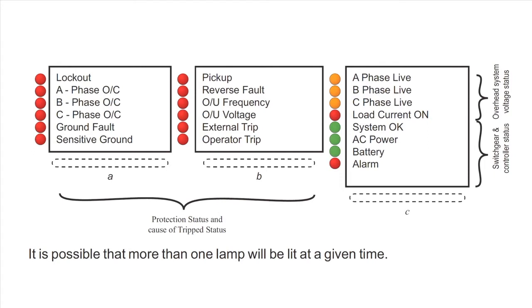The third bank of status LEDs provides information regarding the switchgear and control status, as well as the overhead voltage status. A, B, and C phase live. The source or load side bushing of the relevant phase is live. These 3 LEDs are orange in color when active. Load current on. This LED is red when a load current of more than 2 amperes is flowing through the switchgear. System OK. The controller is functioning normally when the lamp is green. Maintenance may be required when the lamp is flashing red.